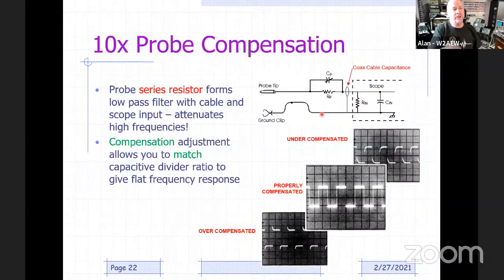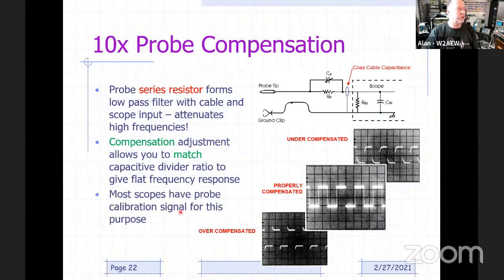Or if all you have is a conductive one, you adjust it, pull it out, make sure it's good, and adjust it again. But the good thing is, if you only have one scope, you just have to make adjustments on your probes once and then forget about it. But the problem is some people forget about it from the get-go and never do it. So again, most scopes have got that calibration signal for that purpose.